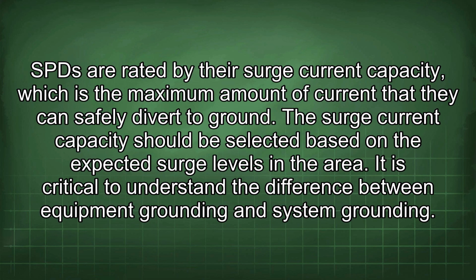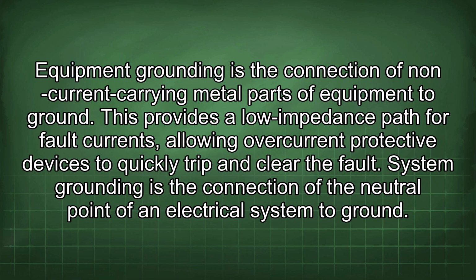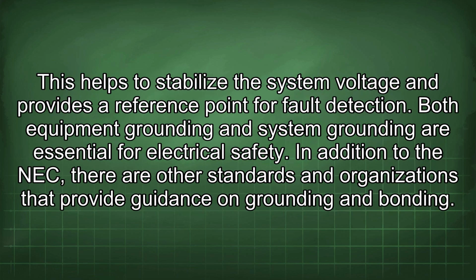It is critical to understand the difference between equipment grounding and system grounding. Equipment grounding is the connection of non-current carrying metal parts of equipment to ground. This provides a low impedance path for fault currents, allowing overcurrent protective devices to quickly trip and clear the fault. System grounding is the connection of the neutral point of an electrical system to ground. This helps to stabilize the system voltage and provides a reference point for fault detection. Both equipment grounding and system grounding are essential for electrical safety.